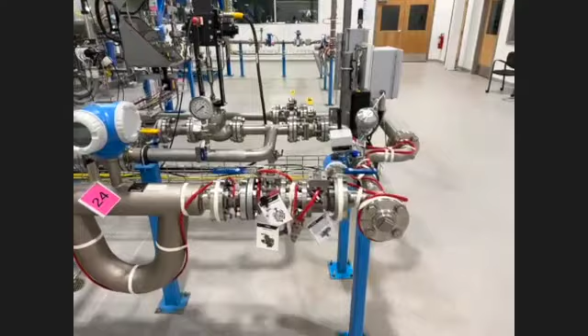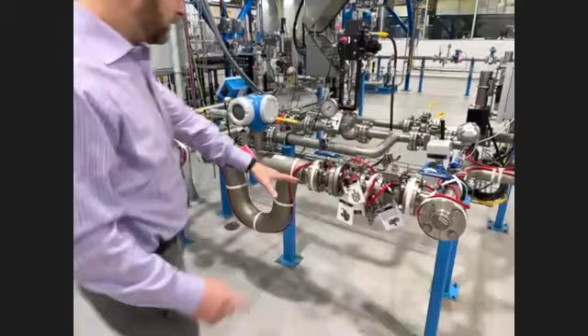Absolutely. That's a great question. Thank you for asking that. I'm going to have Jeff hold the phone so I can maybe give you a better visual. With the flow meter here? Yeah. So we're looking at this valve right here. I believe what he was asking is whether there is a specific way to apply the cable to a valve or any item in here that you don't want trapped. For example, like you mentioned, if you just candy cane around it, when you do need to pull this out and service it, it will lock it in, causing you to need to cut it to gain access to that valve.